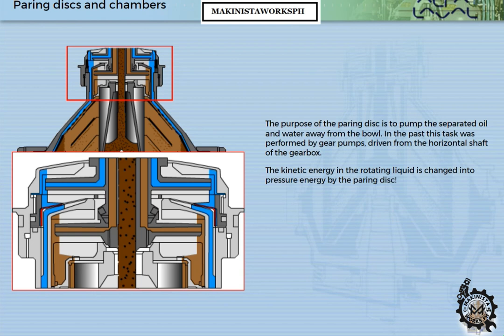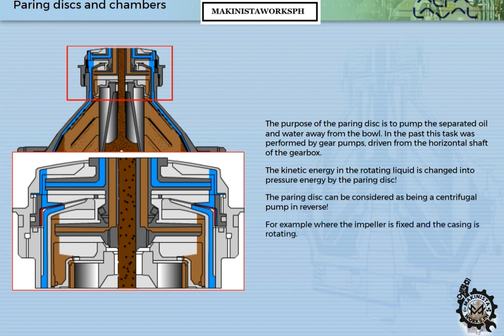The kinetic energy in the rotating liquid is changed into pressure energy by the paring disc. The paring disc can be considered as being a centrifugal pump in reverse — where the impeller is fixed and the casing is rotating.